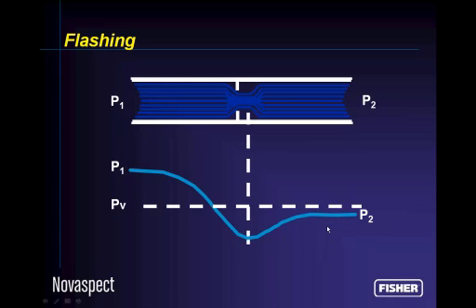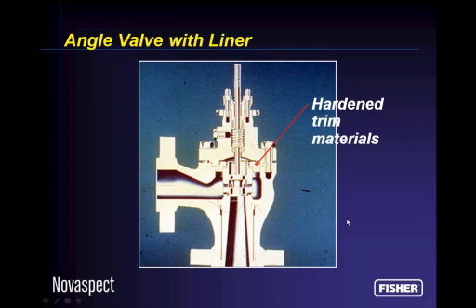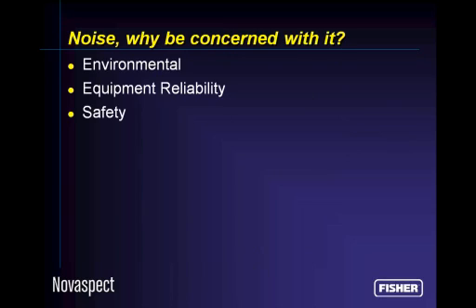It's not cavitating, therefore we don't need a very expensive anti-cavitation trim, but nevertheless, the fact that we come in as water and we're going through the valve as a water-steam mixture, it's a very abrasive, very erosive mixture. It's like a scouring pad running through your control valve, and we need to do certain things to protect you from that. And we do that with basically the materials that we pick, the architecture of the valves, and the fact that we might use a liner in the outlet of the valve. We're going to make these all very hard materials, and a lot of times we'll use an angle valve so that this flashing fluid doesn't make a tortuous path through a linear globe valve. So by architecture and materials, we try to solve damage from flashing problems.